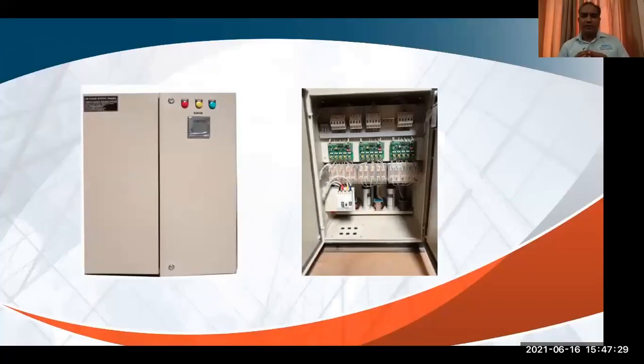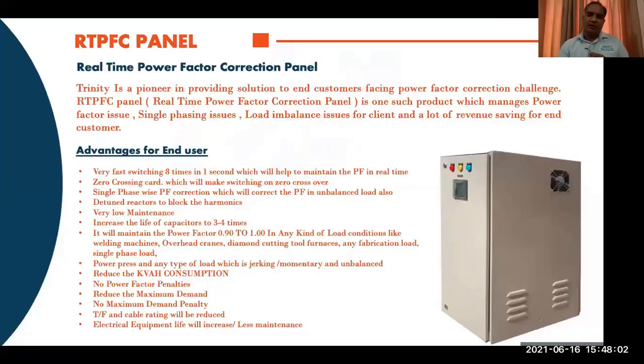We developed a single phase power factor correction panel which controls your PF phase-wise. There is a separate relay card for each of the phases, R, Y, B, and separate thyristor modules for each phase mounted on a heat sink, R, Y, B. Then there are separate single phase capacitors for each phase - for example, if it's a 40 kVAR or 42 kVAR capacitor, then 42 kVAR divided by 3 into each of the three phases. So we developed this product which controls power factor phase-wise.